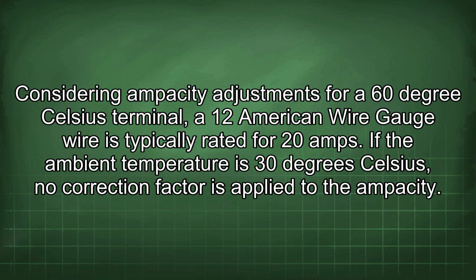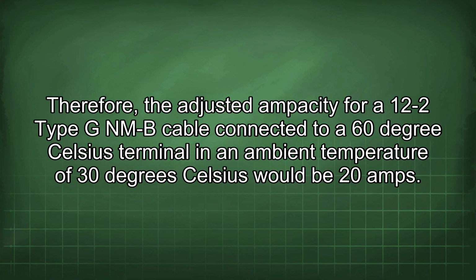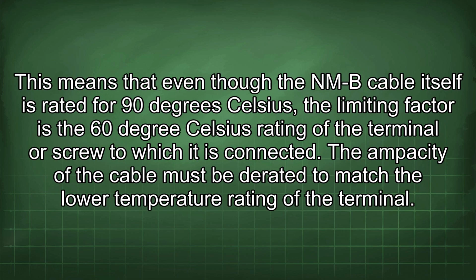amps. If the ambient temperature is 30 degrees Celsius, no correction factor is applied to the ampacity. Therefore, the adjusted ampacity for a 12/2 type NM-B cable connected to a 60 degrees Celsius terminal in an ambient temperature of 30 degrees Celsius would be 20 amps. This means that even though the NM-B cable itself is rated for 90 degrees Celsius, the limiting factor is the 60 degrees Celsius rating of the terminal or screw to which it is connected. The ampacity of the cable must be derated to match the lower temperature rating of the terminal.